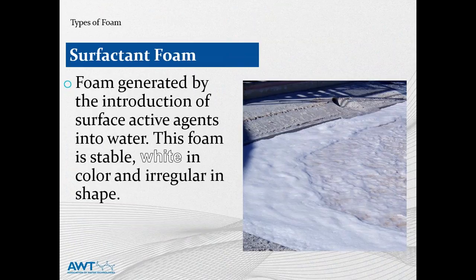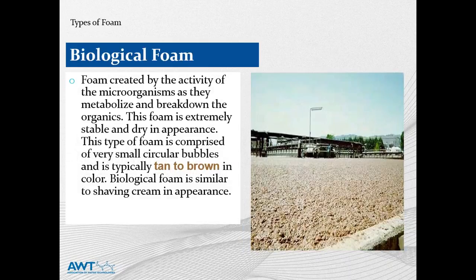Surfactant foam develops when surface-active ingredients are introduced into water. An everyday example is the foam created when you run a bubble bath, or if you've ever shaken a bottle of glass cleaner like Windex. This type of foam is typically white and irregular in shape. Another type of foam often encountered, particularly in municipal settings, is biological foam. This foam is created when microorganisms metabolize and break down organics; it typically looks dry and is a tan or brown color. In a biological system, a little foam is actually quite typical, but at times it can get out of control. Dosing a defoamer will alleviate the foam, however excessive foam is often an indication of an underlying problem such as sludge age.